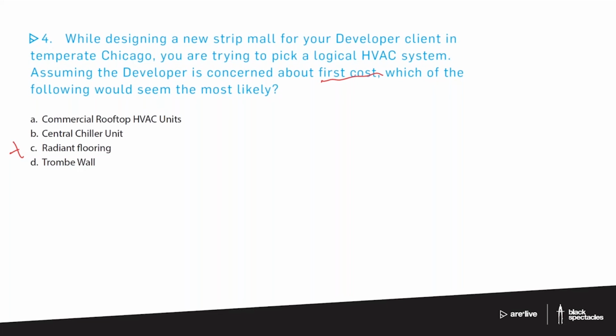It's too flexible. The other thing is, unless you have a very sophisticated HVAC air system focused on the humidity level in the air, you can't really use radiant flooring for cooling. Now, you can, it's just that in everyday reality, if you do that, you're going to get a little condensation on the floor. In a retail spot with public coming in and out all the time, somebody sooner or later is going to slip on that condensation. So you'd never use that on a floor in a commercial setting for cooling. Radiant flooring is out.